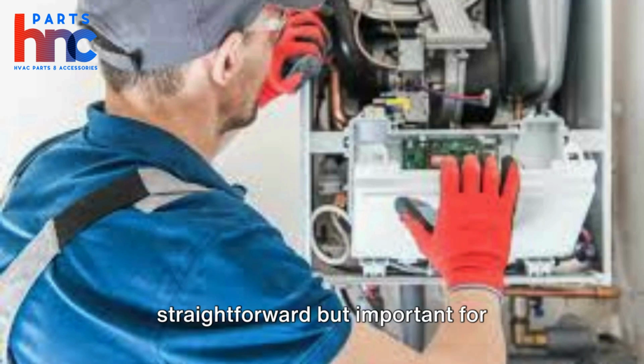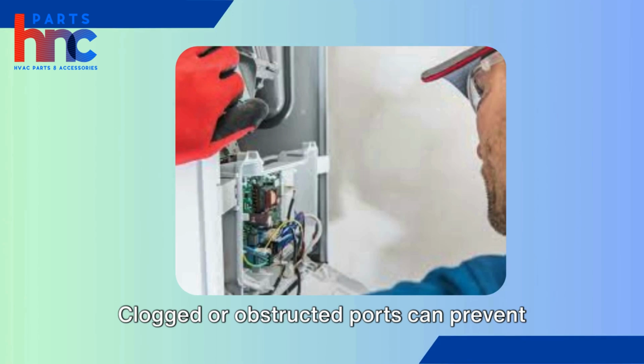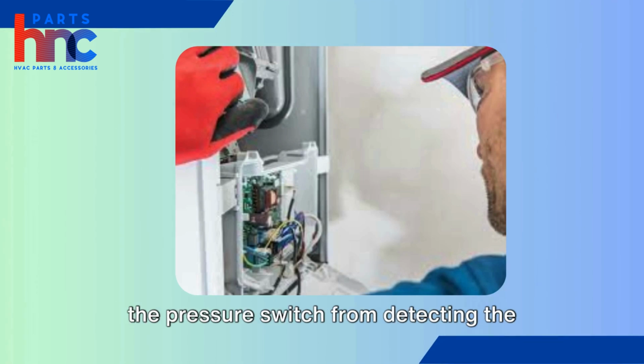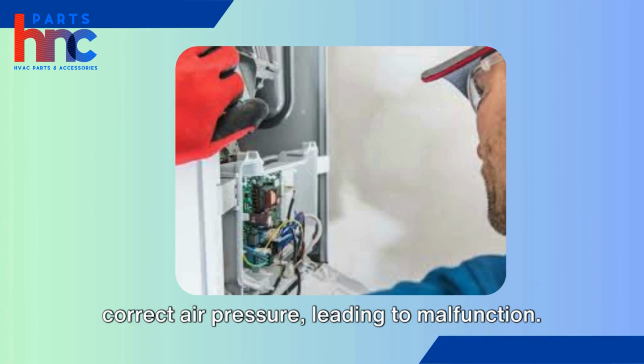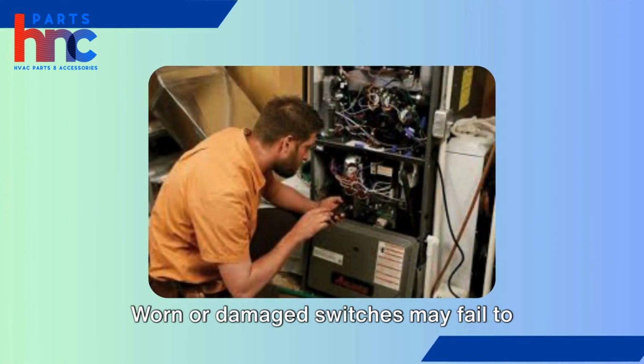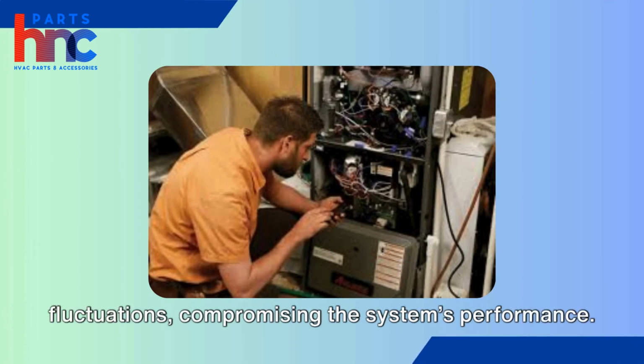Troubleshooting a pressure switch is straightforward, but important for maintaining system efficiency. Clogged or obstructed ports can prevent the pressure switch from detecting the correct air pressure, leading to malfunction. Worn or damaged switches may fail to respond accurately to pressure fluctuations, compromising the system's performance.